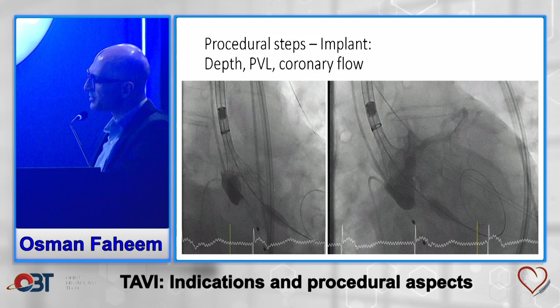Once the valve is in position, you take a root shot and see if you're happy with the position. You can reposition this 3 times. We've done it sometimes up to 5 times. It works okay, but the IFU is 3 times. So you check for coronary perfusion, and you check for valve depth and paravalvular leak.